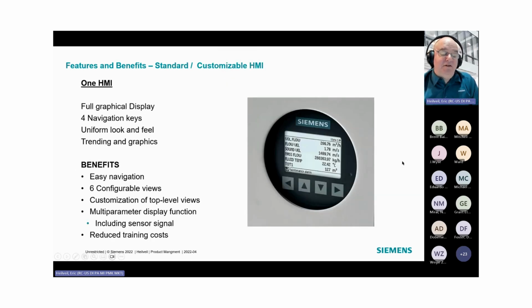Another nice benefit about this device is the display. It is a true multifunction display. As you can see in the picture here, the display can show a host of data points: flow, volume flow, sound speed, temperature, mass flow conversion, totalizer. You can also show just one flow, one display. You can have it in big 3-inch block letters of what your flow is. Or you can actually have the display show you what the waveform looks like. And the waveform is the actual sound signal that the device has.